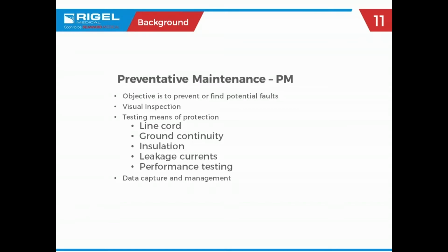Especially when you look at the NFPA 99 standard. How many people test NFPA 99? Oh, come on. Yeah. As I said earlier, that standard, that test gets a little simpler and easier each year. And one big change in the 2018 revision, they added a lot of additional information, a lot of extra verbiage as to why some of the changes have been made. So it's a pretty interesting read. It's not all that expensive, worthy of perhaps being on your hard drive. So anyway, there we have it.